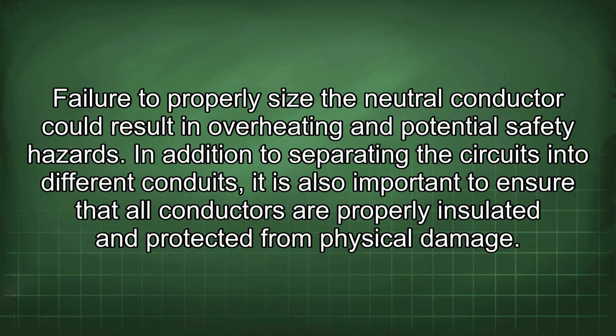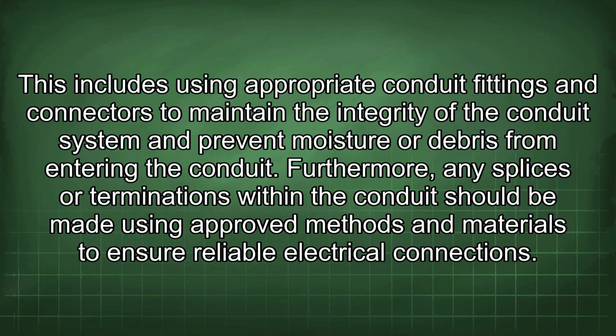In addition to separating the circuits into different conduits, it is also important to ensure that all conductors are properly insulated and protected from physical damage. This includes using appropriate conduit fittings and connectors to maintain the integrity of the conduit system and prevent moisture or debris from entering the conduit. Furthermore, any splices or terminations within the conduit should be made using approved methods and materials to ensure reliable electrical connections.